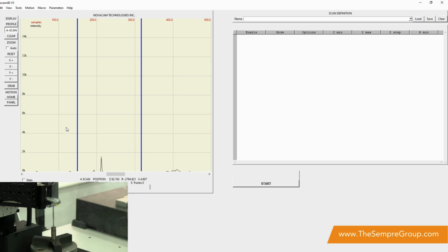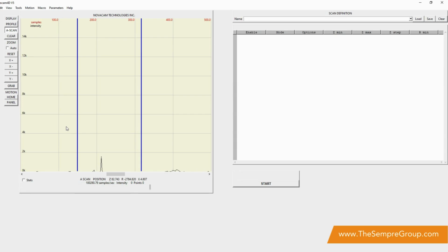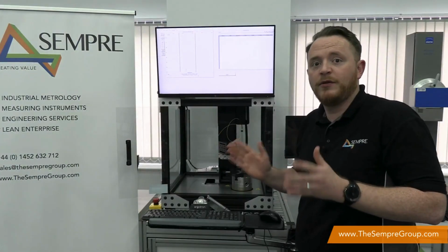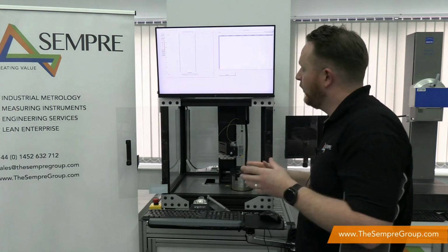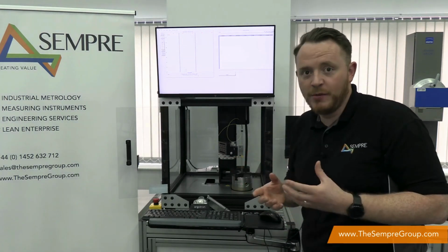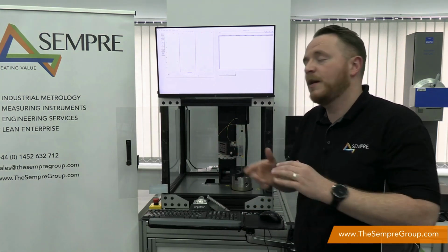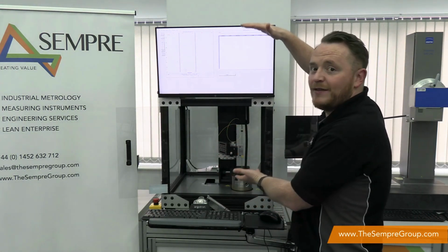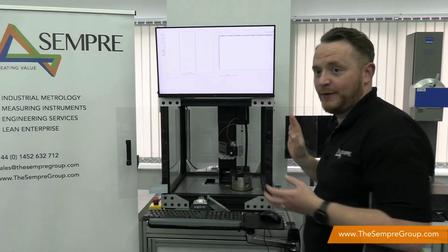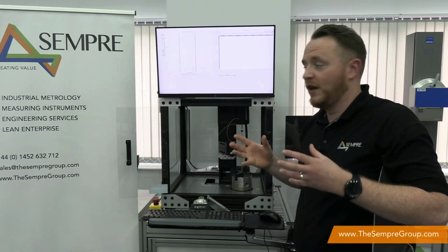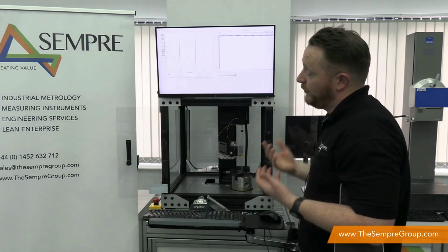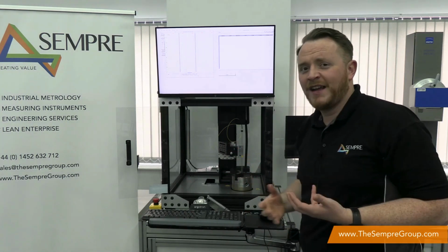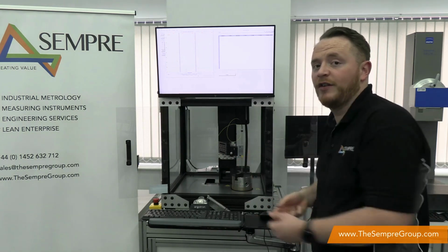Now we can move the position of those blue lines depending on the fit or the diameter that we're trying to measure. This sensor here we're trying to work with at about 5 millimeters, but we do have some sensors that can view up to about 230 millimeters. So depending on the specifics of the application that you might have will depend on the different types of setups. We've got some setups where the Z range is about 2 meters, also with an X range of about half a meter. So there's lots of different types of systems. When you're talking about Novacam, you're talking more about a technology as opposed to a specific off-the-shelf product.